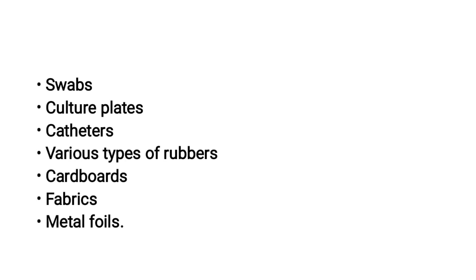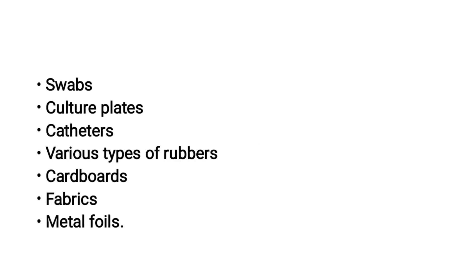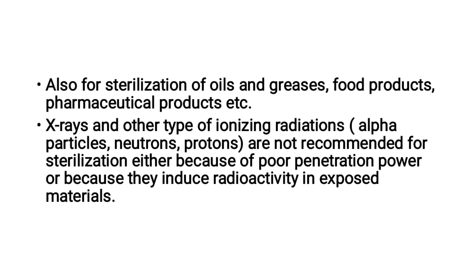Ionizing radiation is used for sterilization of items such as plastic syringes, swabs, culture plates, catheters, various types of rubber, cardboard, fabrics, and metal foils. It is also used for sterilization of oils, greases, food products, and pharmaceutical products. Alpha particles, neutrons, and protons are not recommended for sterilization either because of poor penetration power or because they induce radioactivity in exposed materials.